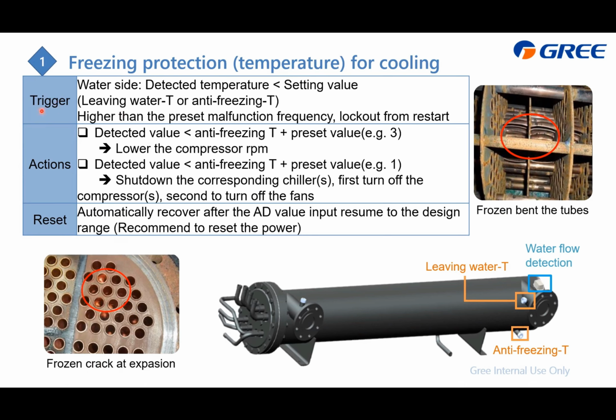And here is how the system will display this error. Why? From the water side, we detect the water temperature at the leaving water and also the anti-freezing. We check if it is lower than the setting value, and we trigger this error. And of course, if this error occurs more than the preset malfunction frequency, like 1 hour, 3 or 4 times, we will lock out the system from restart.